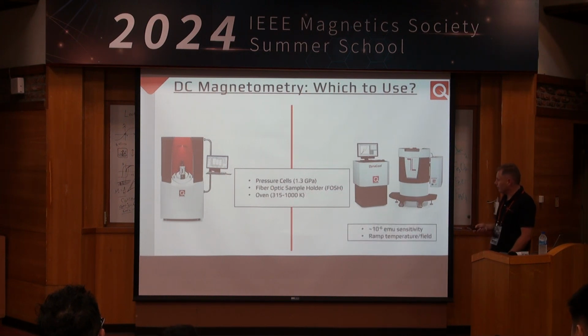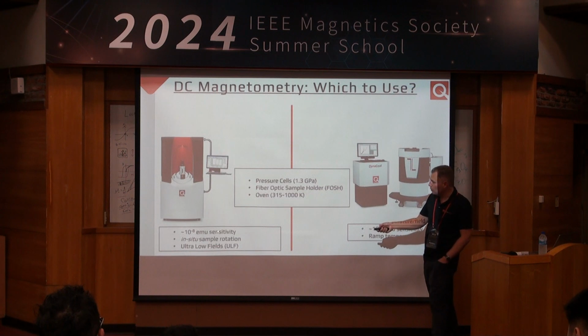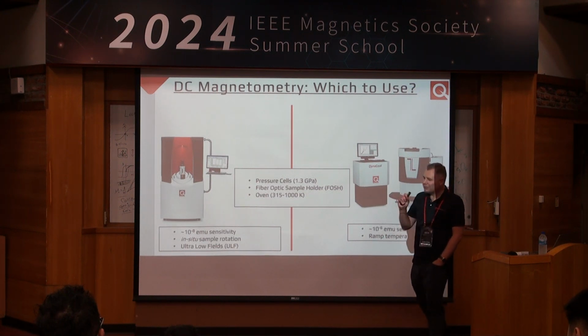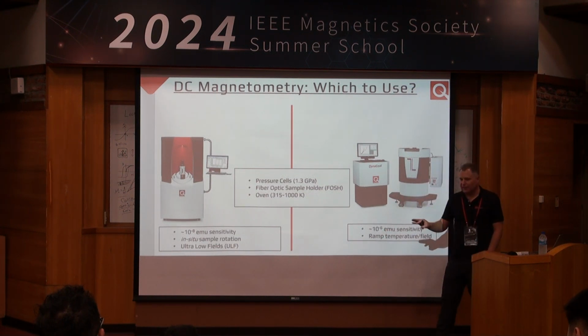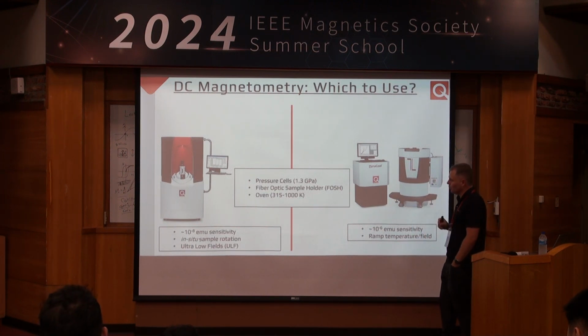Where do they start to differ? So again, here, roughly micro-emu level of sensitivities. But you can measure while ramping the temperature and magnetic field, actually quite quickly. So again, good for fast measurements. Here, we get 2 orders of magnitude more sensitivity, but it's best not to measure while ramping the magnetic field. You will destroy a lot of the sensitivity. So it can be a little bit slower in that case.